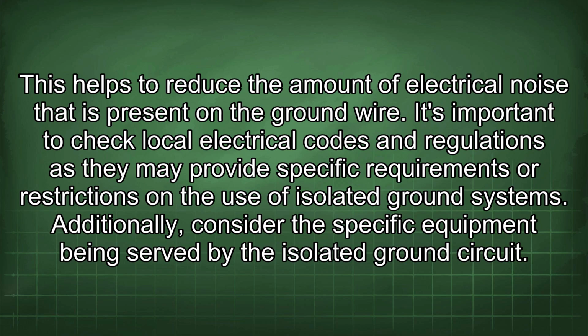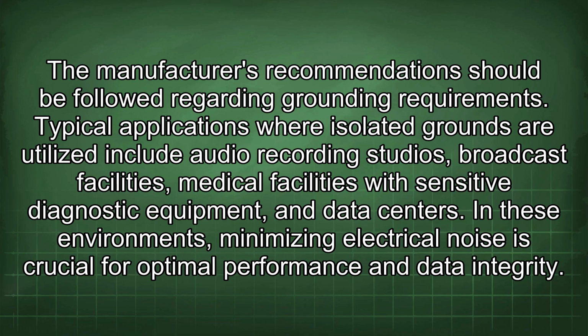It's important to check local electrical codes and regulations, as they may provide specific requirements or restrictions on the use of isolated ground systems. Additionally, consider the specific equipment being served by the isolated ground circuit. The manufacturer's recommendation should be followed regarding grounding requirements. Typical applications where isolated grounds are utilized include audio recording studios, broadcast facilities, medical facilities with sensitive diagnostic equipment, and data centers. In these environments, minimizing electrical noise is crucial for optimal performance and data integrity.